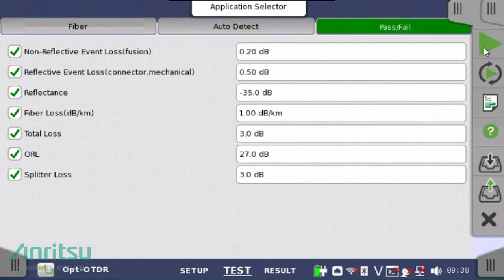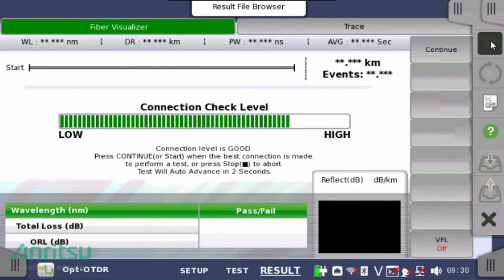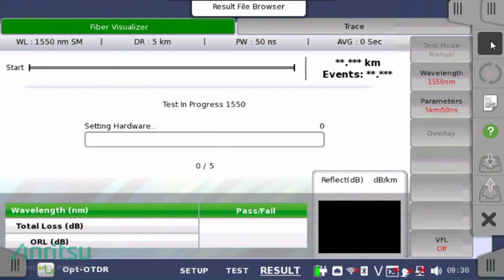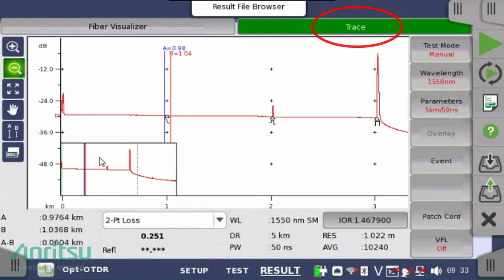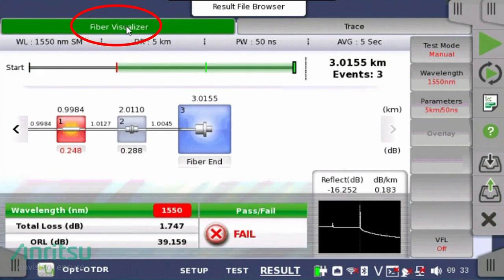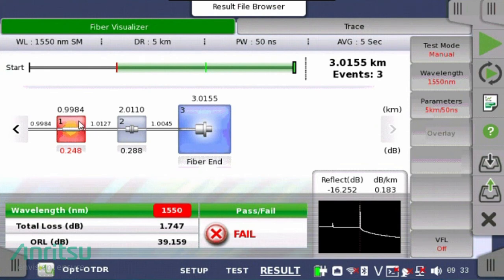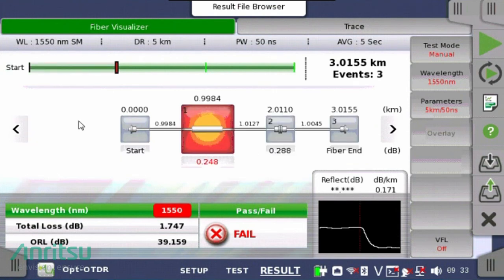Once your settings are complete, press the large green triangle in the top right-hand corner of the screen to begin the OTDR measurement of the optical fiber under test. The first test is the connection test, followed by the OTDR measurement. You can switch between OTDR trace view and Anritsu's award-winning Fiber Visualizer view of the same OTDR measurement. The Fiber Visualizer displays all of the events during the OTDR measurement.